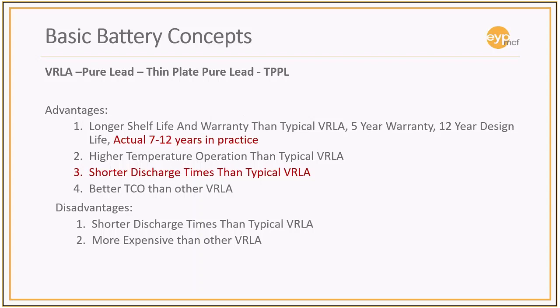The effect of going too short, or designing too short a time, means that you don't have any real degradation time. So if you designed a flooded cell battery for 5 minutes, you wouldn't get 5, 4, 3, 2, 1 minutes. You'd get like 2 or 3 minutes, and then it would just fall off. These valve regulated batteries in the thin plate environment allow you to design to a shorter discharge time. We're seeing more and more colo environments where, for the economics of the situation, you know that your generator needs to be up in 10 seconds or 15 seconds.